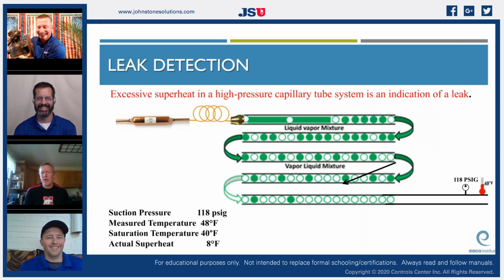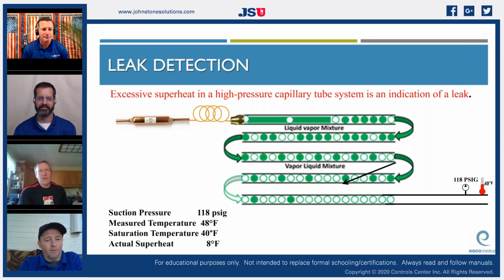Interesting slide here. It tells you if you have high superheat on a cap tube or a piston, you might have a leak. It's probably low on charge with high superheat, considering all the other factors are good, like airflows and such as this. We use subcooling on a thermal expansion valve and electronic expansion valve to determine if the amount of refrigerant is adequate. So just a couple ways to determine if indeed it was ever correct to begin with. High superheat or low subcooling might be an indication that you've lost some of the initial charge.